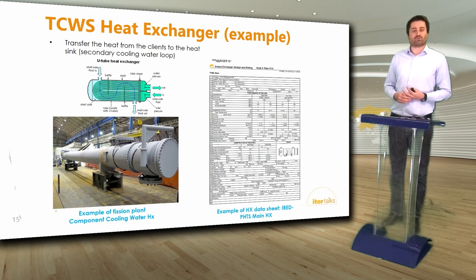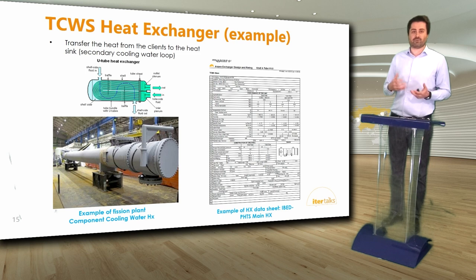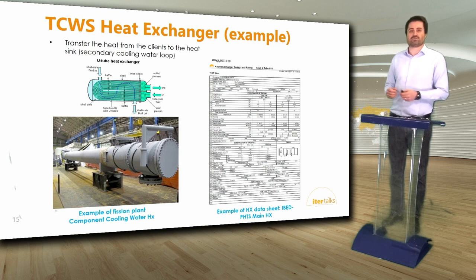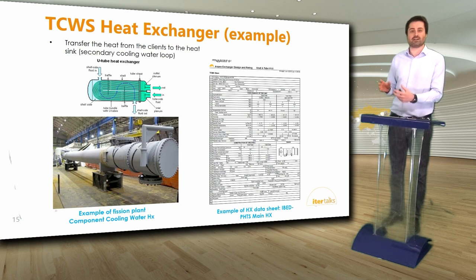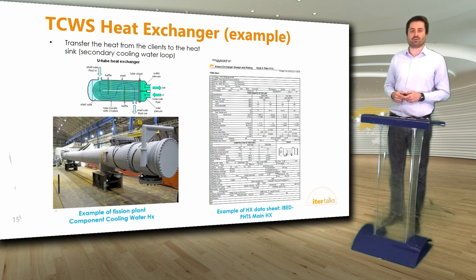Another major component is heat exchangers. The largest are for the IBED PHTS — the system cooling the in-vessel components. Their function is to cool the water so that cold water can be provided to clients. The heat extracted from clients such as in-vessel components is transferred to the secondary cooling water system through these heat exchangers. They are the functional interface between the TOKAMAK cooling water system and the secondary cooling water system. Different typologies of heat exchangers are used depending on the required heat load and temperature difference.